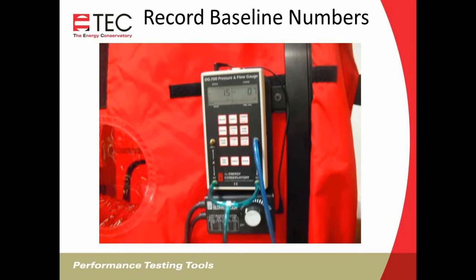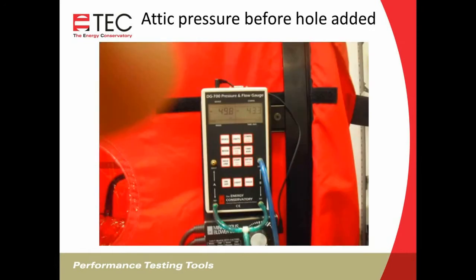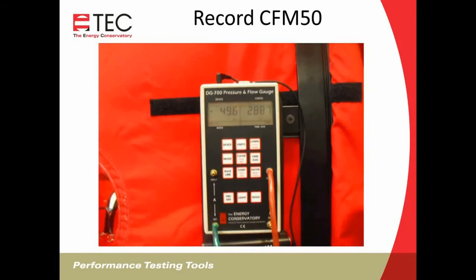First, we're going to record baseline numbers, both house to outside and attic to outside. What the software wants us to do is set the time averaging to 5 seconds and record three numbers, both house to outside and attic to outside. Then we'll bring the house to 50 and record the attic pressures. So we'll bring the house to 50, record our attic to house pressure, and then we'll switch the hoses around on channel B, keep the house at 50, and record our CFM at 50.